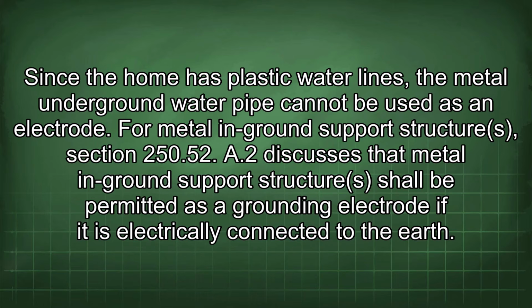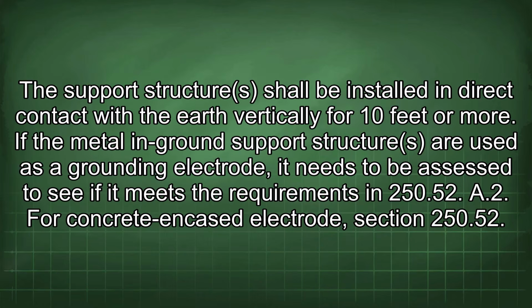(A)(2) discusses that metal in-ground support structures shall be permitted as a grounding electrode if it is electrically connected to the earth. The support structure shall be installed in direct contact with the earth vertically for 10 feet or more. If the metal in-ground support structures are used as a grounding electrode, it needs to be assessed to see if it meets the requirements in 250.52(A)(2).